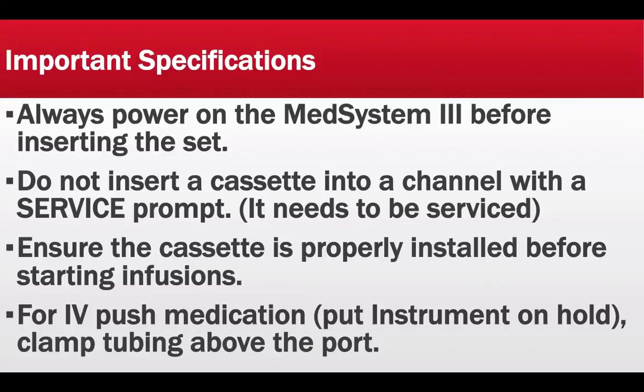Important specifications continued. So always power on the MedSystem 3 before inserting the set. Do not insert a cassette into a channel with a service prompt. It needs to be serviced. Ensure the cassette is properly installed before starting infusions. And for IV push medication, the manufacturer states that you have to put the instrument on hold, clamp the tubing above the port, and then push your medication, and then resume your administration.